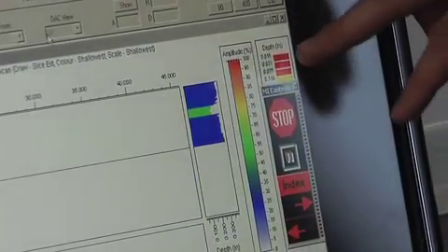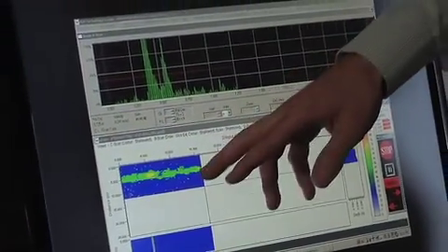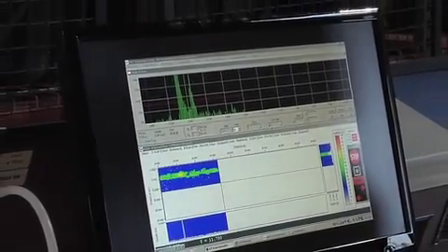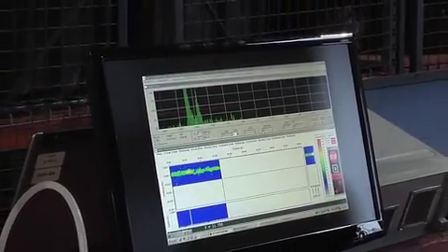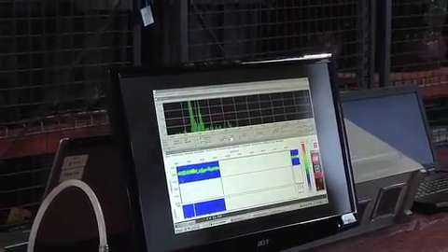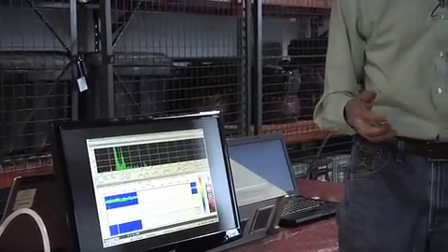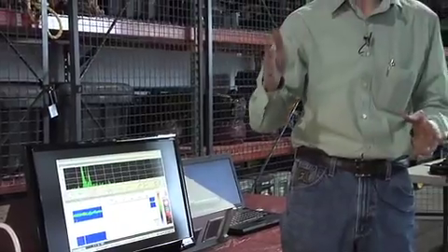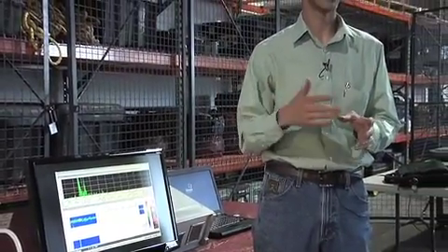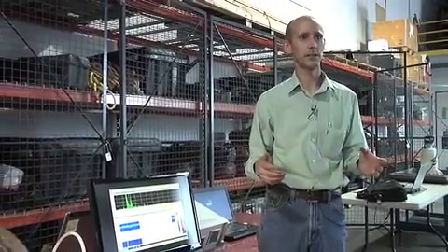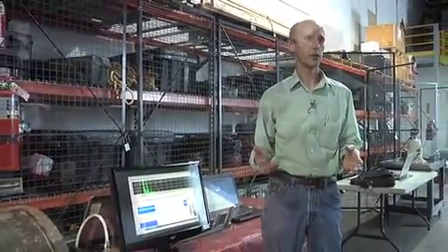We have our color scale over here explaining the colors, the different thicknesses each colors are. We could make this as broad or as few colors as the client wants. If he's just wanting to know what his minimum thickness is, say his cutoff point is quarter of an inch, anything below that he needs to know about, he doesn't care about anything above it, we'll use two colors.